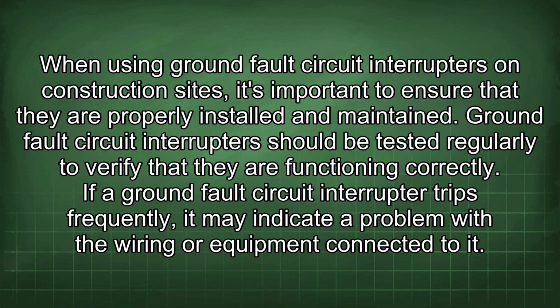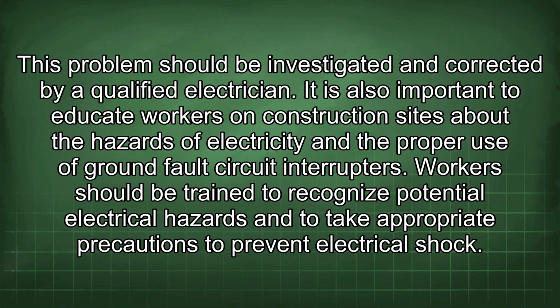When using ground fault circuit interrupters on construction sites, it's important to ensure that they are properly installed and maintained. Ground fault circuit interrupters should be tested regularly to verify that they are functioning correctly. If a ground fault circuit interrupter trips frequently, it may indicate a problem with the wiring or equipment connected to it. This problem should be investigated and corrected by a qualified electrician. It is also important to educate workers on construction sites about the hazards of electricity and the proper use of ground fault circuit interrupters.